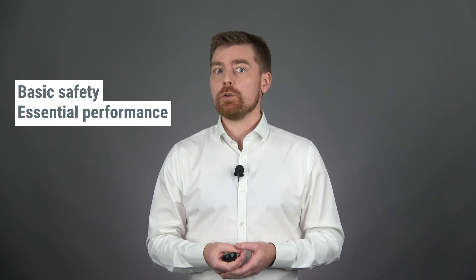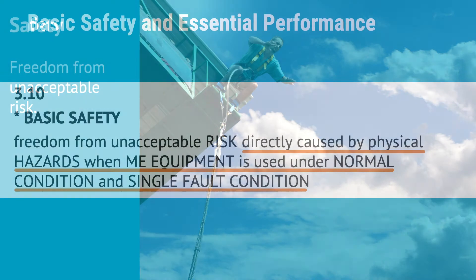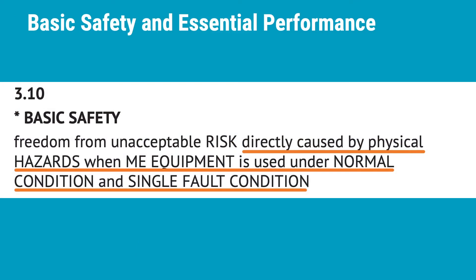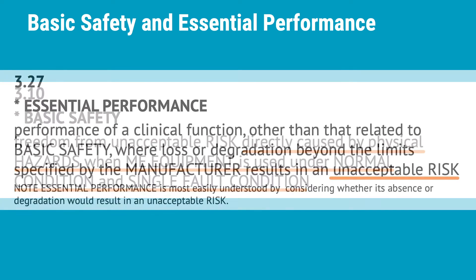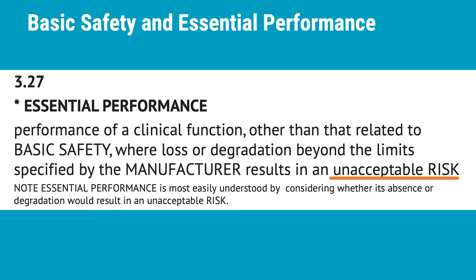Remember, the goal was to get an understanding of what basic safety for medical devices is. Let's start with the definition of safety, which comes from ISO 14971. Safety is defined as freedom from unacceptable risk. What is then basic safety? Basic safety is to avoid unacceptable risk directly caused by physical hazards, when medical electrical equipment is used under normal condition and single-fault condition. This is a slightly more narrow concept compared to safety in general. And essential performance has the same objective: to avoid unacceptable risk.